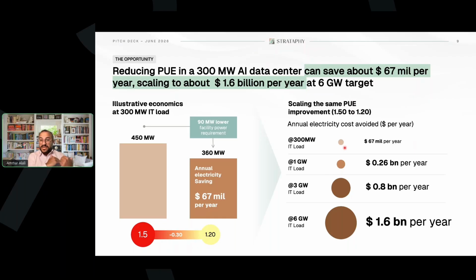Now, if you assume that the average PUE is 1.5, and you're able to reduce that average PUE to 1.20, that's a significant, meaningful reduction that could be represented in lower facility power requirement by 90 megawatts. That also could be represented financially by a reduction of operational expenses. Here we're assuming roughly 4 cents per kilowatt hour. Usually they get subsidized prices because they either generate power or tap into power resources close by, or are subsidized by a different government. If we go with that number, you're looking at roughly $67 million a year that you could theoretically achieve by reducing your PUE from 1.5 to 1.2. Now, as you scale this number, obviously there is a linear relationship, and here we're making a lot of assumptions.